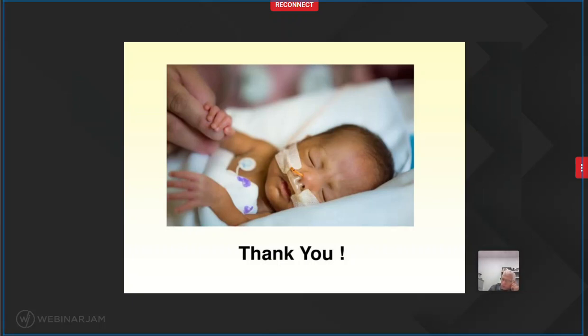One of the questions referred to what type of sensor is the best for newborns. There are basically three types of sensors. One is flow, one is pressure, and the other one, the newer one, is NAVA, which is the diaphragm electromyography. Each one of these sensors has pros and cons. The advantages of the flow sensors are that they have a very quick response, they're very sensitive, and they are non-invasive. The disadvantages of the flow sensor are that they are affected by leaks and they add extra dead space and weight. The pressure sensors are good because they don't add extra dead space or weight, and they're also non-invasive, but they have a longer trigger delay, and the sensitivity is not as good as the flow sensor. So they're usually not used much in neonatal ventilators.